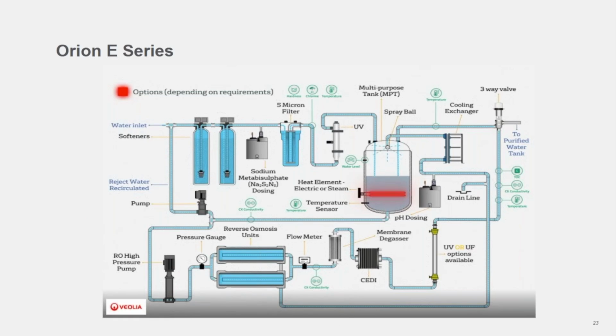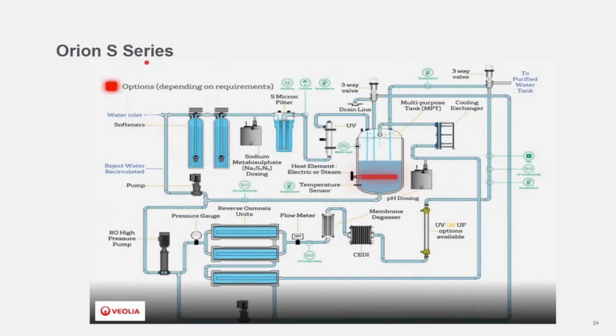If we move on to the S series, so this is the full sustainability model. So it incorporates all those good things on the E series of the cooling exchanger for reduced water during recycle, and we drop the flow during recycle. But during the service run, this has the additional RO membrane, as you can see on the bottom there. So this is a recovery RO membrane. And this takes the concentrate from the main RO, and we put it through the recovery RO there, and the permeate then goes back into the multi-purpose tank to go through the system again.